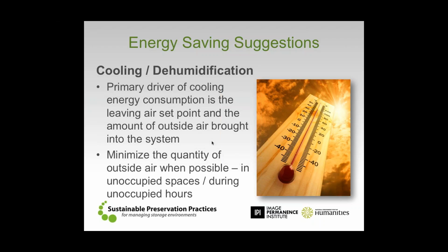And if we bring in too much of that air, then it just increases the amount of work that we have to do. So if we're talking about storage scenarios, or even if we're talking about patterns of occupation in a space that would normally house people, the goal, or something to think about, is really to try and minimize the quantity of outside air whenever possible. You know, if there isn't anyone in the building between the hours of 6 at night and 6 o'clock in the morning, then outside air is, for all intents and purposes, unnecessary.